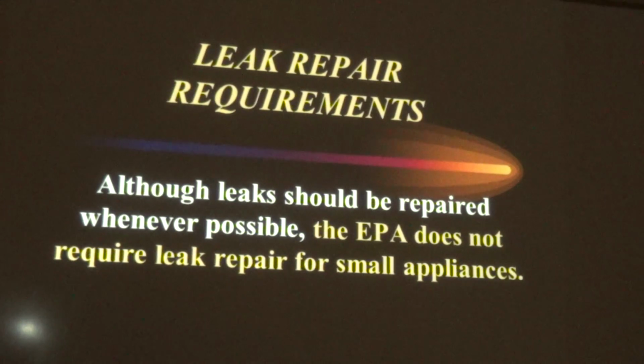Leak repair requirements. We're talking about type 1 equipment now, a 5 pounds or less appliance. There is no rule from the EPA that says you have to make a repair to this equipment. No rule, no requirement. What they will say is that you should, whenever possible, repair leaks or prevent leaks to help the environment, but there's not a legal requirement for that.